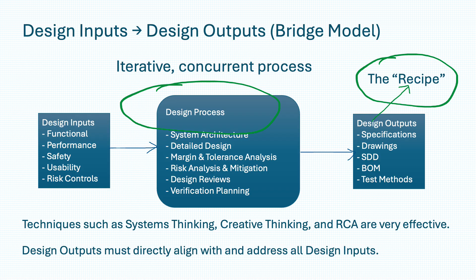Then comes verification and validation. From the design output phase we just completed, we have a recipe and have also built some prototypes. Now comes the moment of truth. We must prove it actually works, and we do so in two distinct and important ways. Pay close attention because this is a crucial distinction that confuses many people. Verification versus validation. Verification asks, did we build the product right? It's a technical check. It's an engineering check. Validation, on the other hand, asks, did we build the right product? It's a user-focused check. It's a validation check by the user.